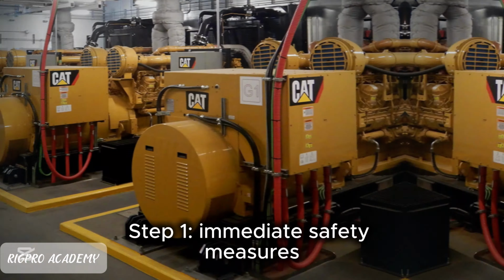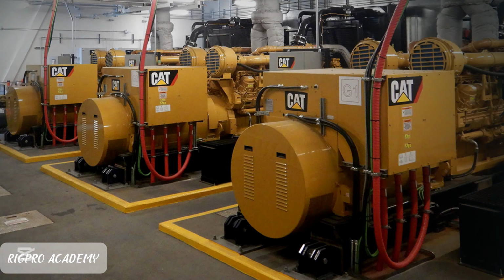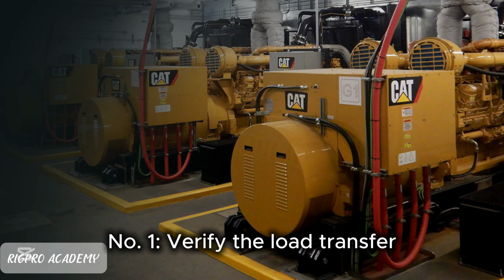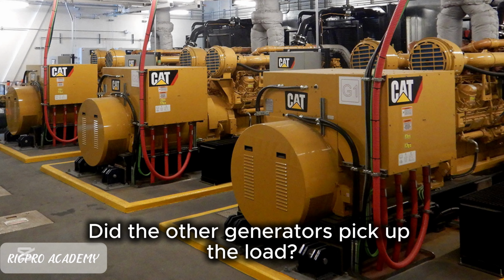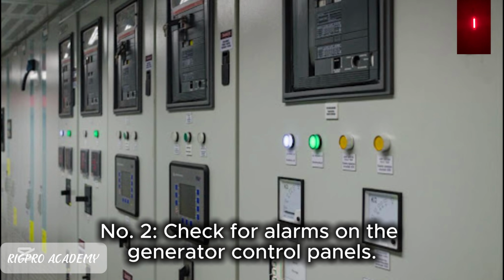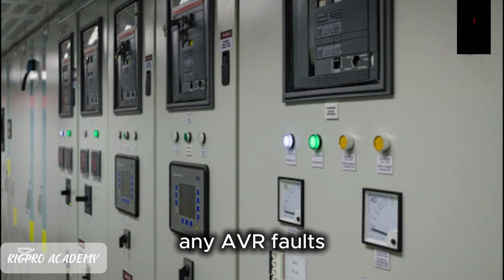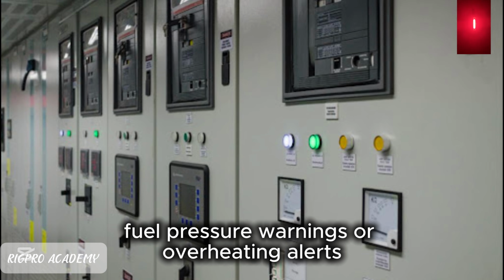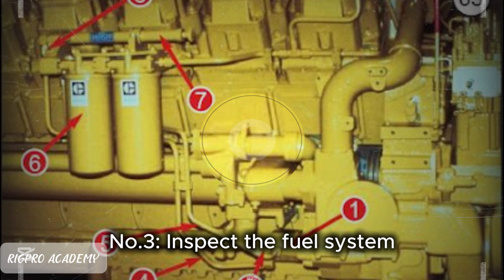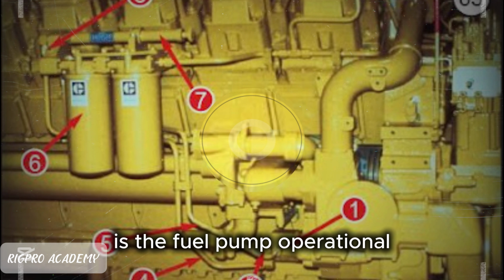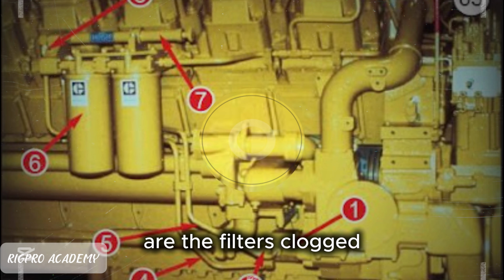Step 1, immediate safety measures. Number 1, verify the load transfer. Did the other generators pick up the load? Number 2, check for alarms on the generator control panels, any AVR faults, fuel pressure warnings, or overheating alerts. Number 3, inspect the fuel system. Is the fuel pump operational? Are the filters clogged?